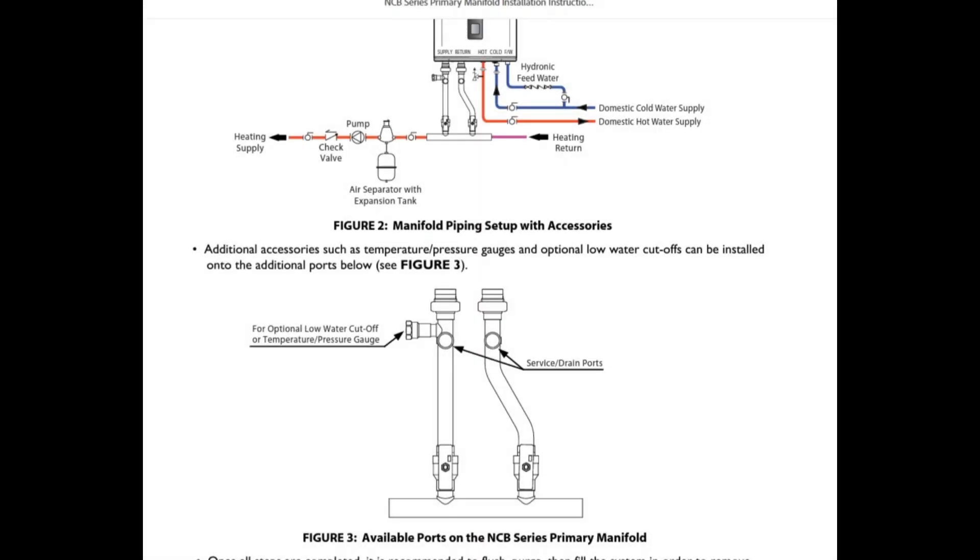So going back to the beginning with this manifold here, what we basically have is called a hydronic separator. You're going to hear it referred to a lot of times as closely spaced T's because we got T here and a T here and they're closely spaced. Pretty self-explanatory. But here we have what this basically does is it creates two separate loops that kind of come together in the same place. So you have a primary loop here where water can circulate and get reheated based on that five or six gallon per minute internal circulator pump.